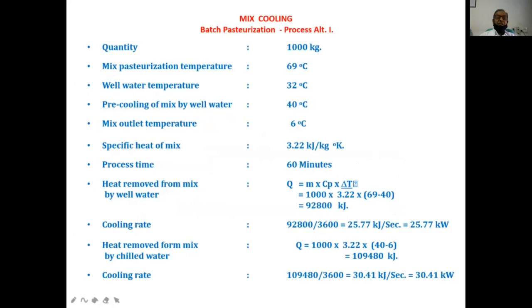The specific heat of the mix is 3.22 kilojoule per kilogram degree Kelvin. Friends, you know 4.18 is the specific heat of water, but this contains fat also, SNF and sugar. That's why the specific heat of the mix is slightly lower than water, that is 3.22 kilojoule per kg degree Kelvin. And the process time is 60 minutes. So how much time is required? We have considered 60 minutes; it can be 30 minutes, it can be 60 minutes also for cooling, because we are calculating the cooling load.